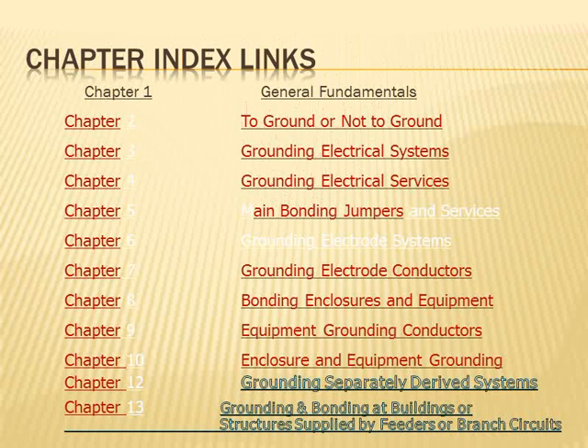What you deal with is like a 9-volt battery brought to a light, and the light goes on. In a grounded system, you take that negative and tie it to a water pipe or a rod. That's 95% of what we do in the power industry. The 5 to 10% that we also do is the ungrounded system, where the battery is not tied in any way, shape, or form to the ground. That applies for DC as well as AC. So there is the ungrounded system, with its advantages and disadvantages.